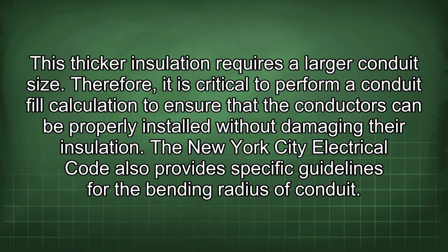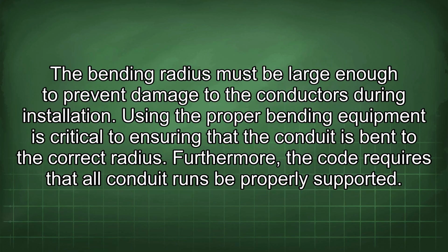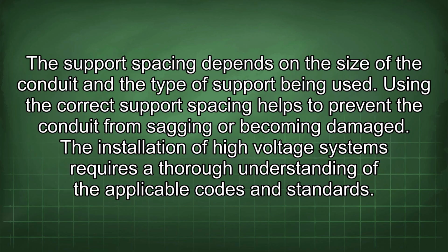damaging their insulation. The New York City Electrical Code also provides specific guidelines for the bending radius of conduit. The bending radius must be large enough to prevent damage to the conductors during installation. Using the proper bending equipment is critical to ensuring that the conduit is bent to the correct radius. Furthermore, the code requires that all conduit runs be properly supported. The support spacing depends on the size of the conduit and the type of support being used. Using the correct support spacing helps to prevent the conduit from sagging or becoming damaged.